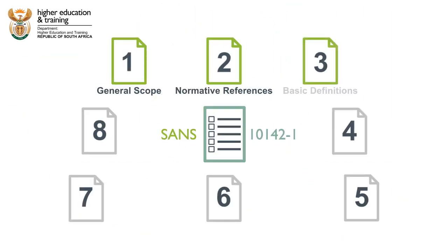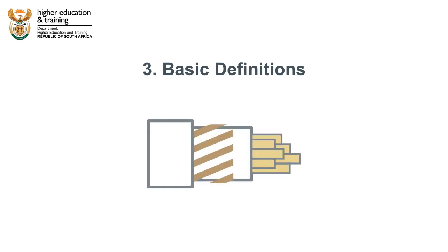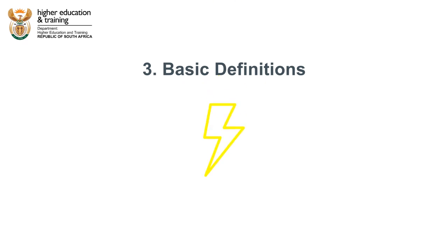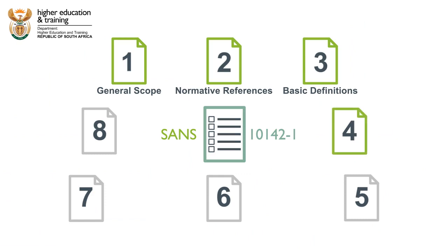We also need to be familiar with all the referenced codes as well. Clause 3 provides some basic definitions. For example, that an armored cable is a cable that has a covering of metallic wires or galvanized steel wires or steel tape as a protection against mechanical damage. Or, that low voltage is voltage that does not exceed 1000 volts alternating current or 1500 volts direct current.